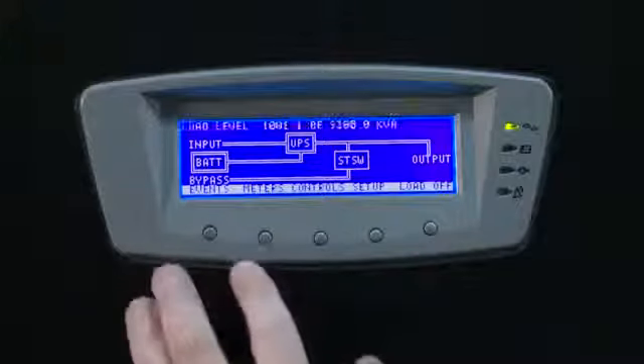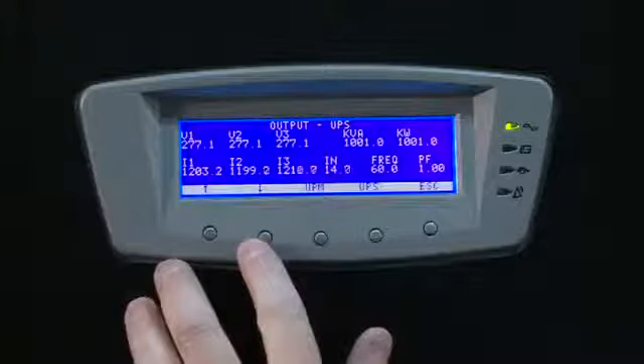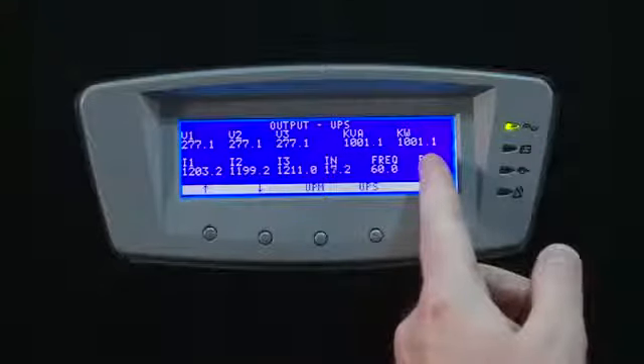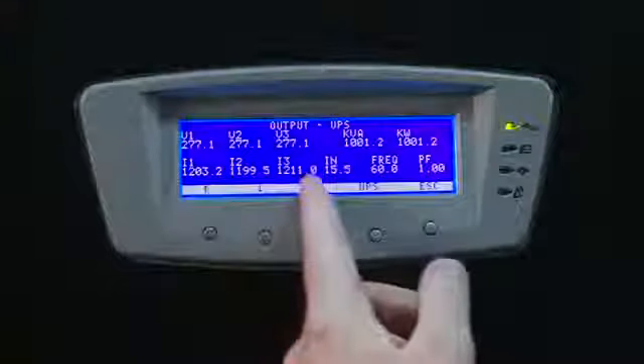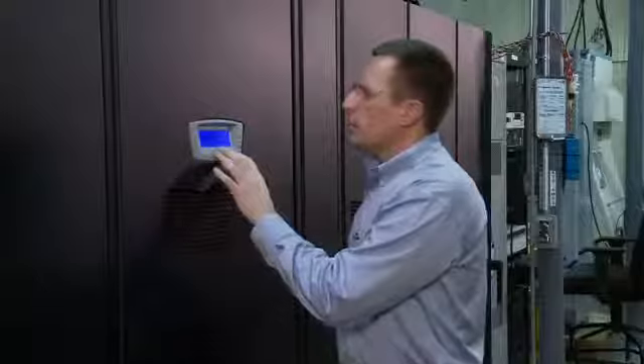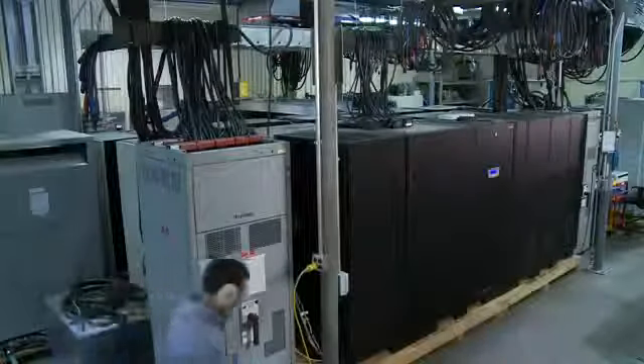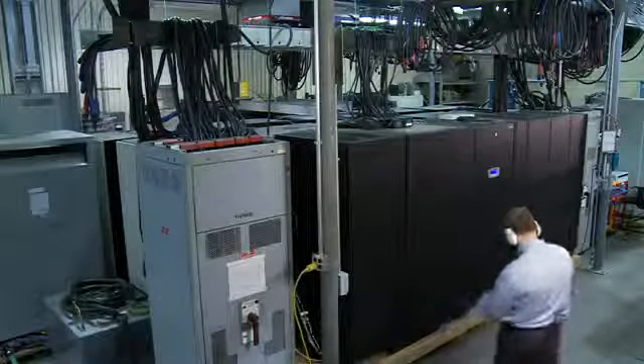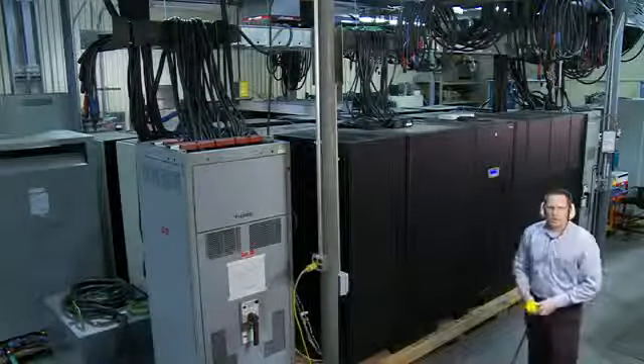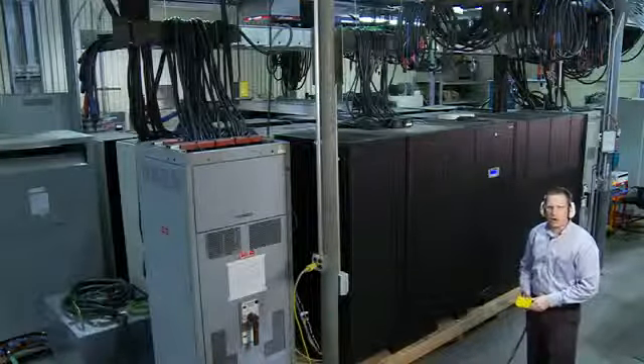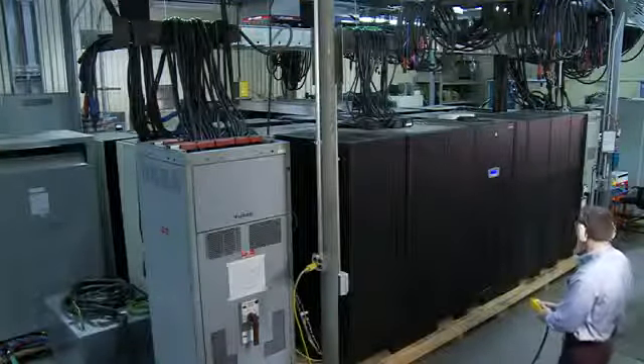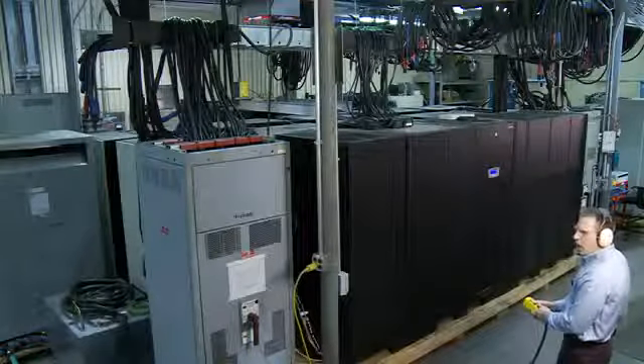As you can see here on the meter screen, the unit is fully loaded and the current is presented here as such. With the system ready, now let me prepare the faulting breaker for test. And now we're prepared to perform the fault. Fault!